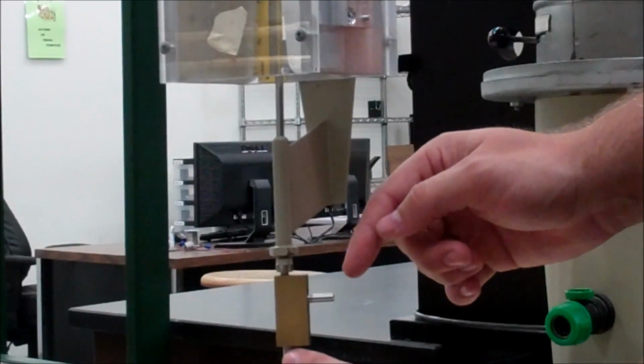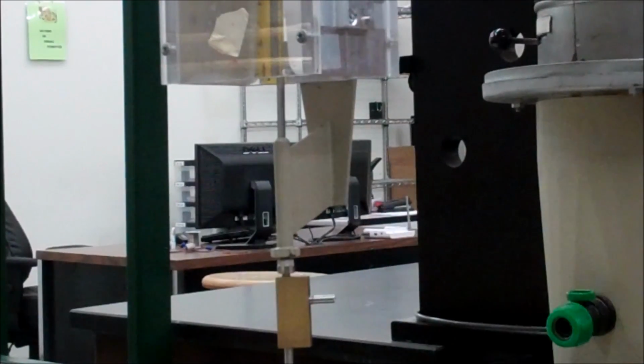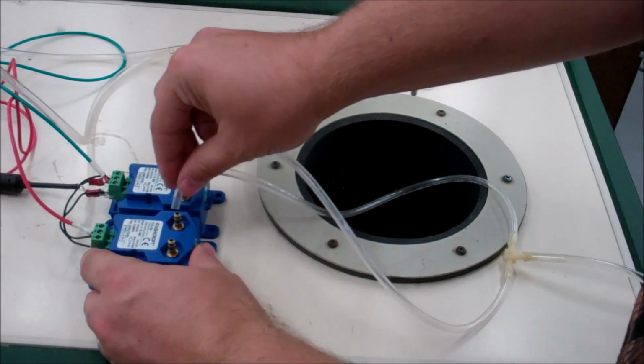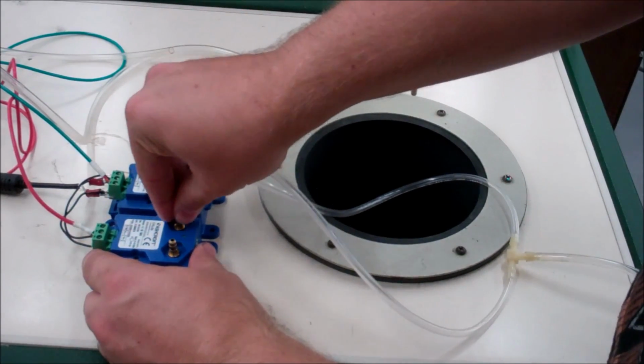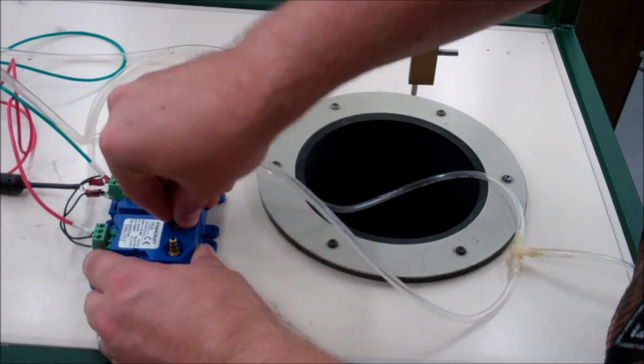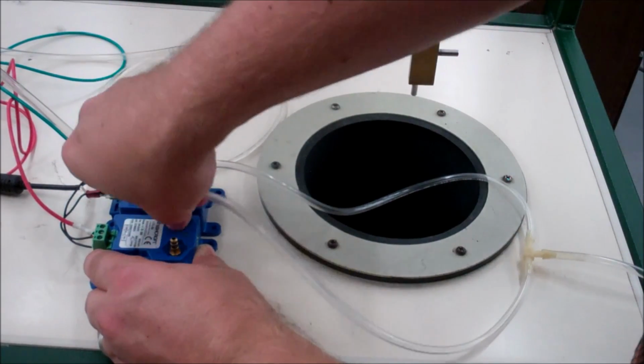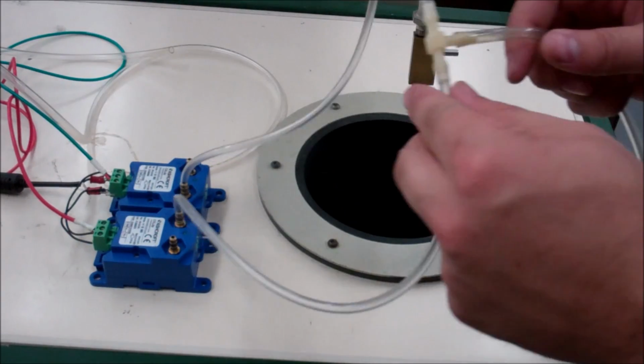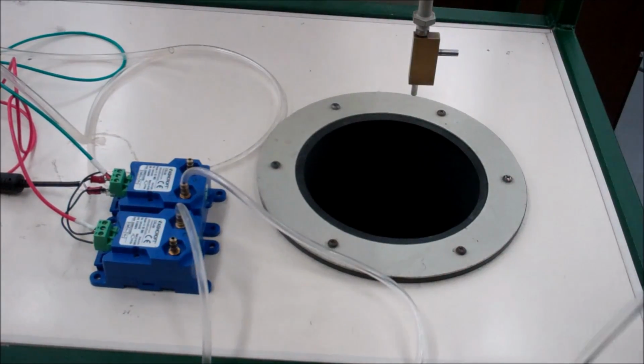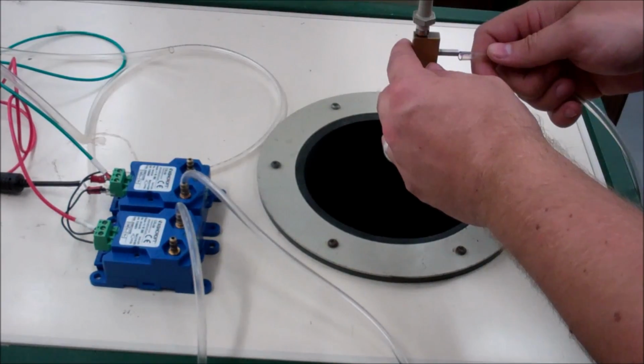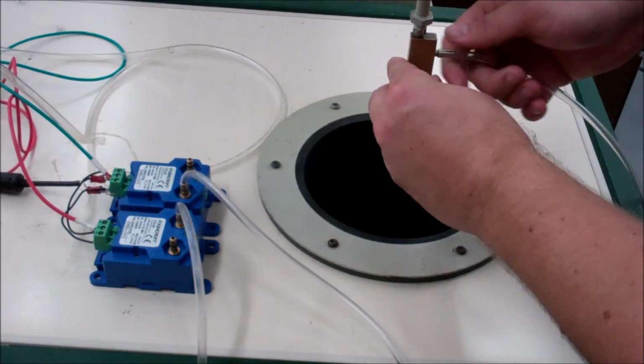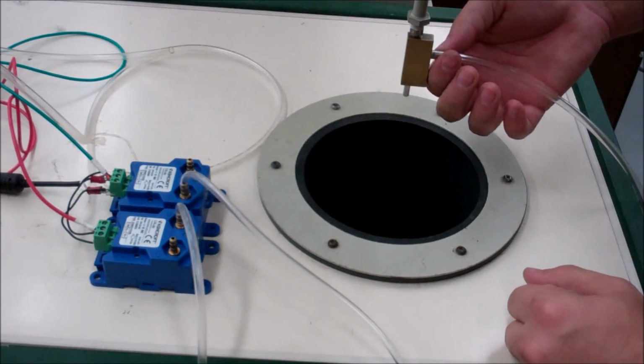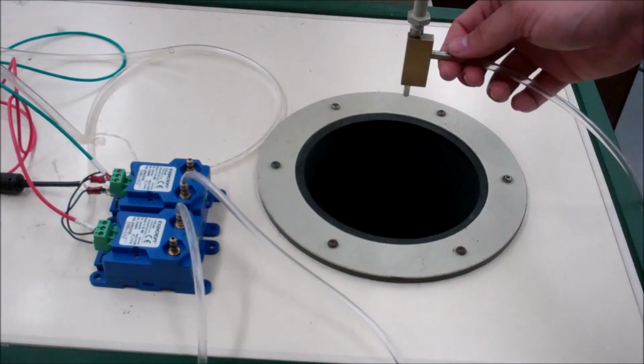This tube is a stagnation tube, this tube is a static tube. Tubes to the pressure transducers. One you can connect to the high port, and that's your static pressure one. And the other one you connect to the low port.